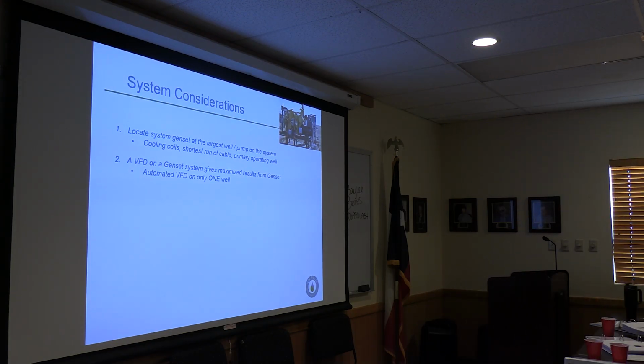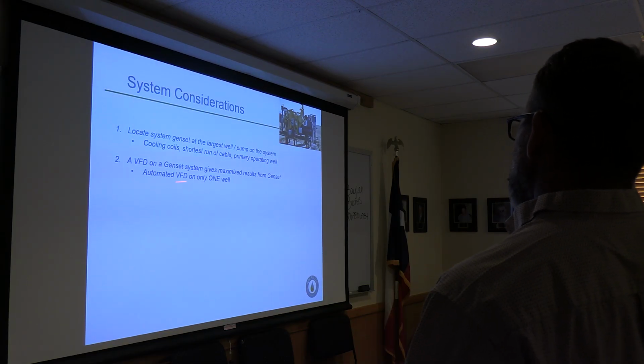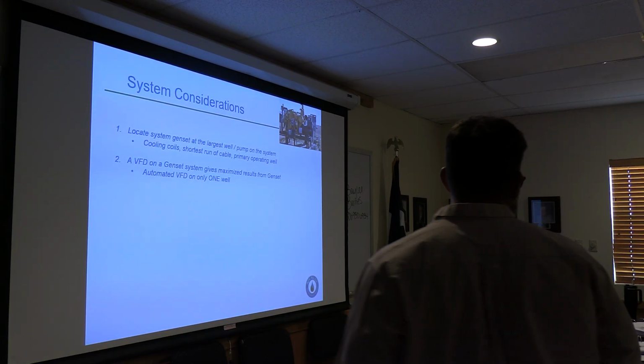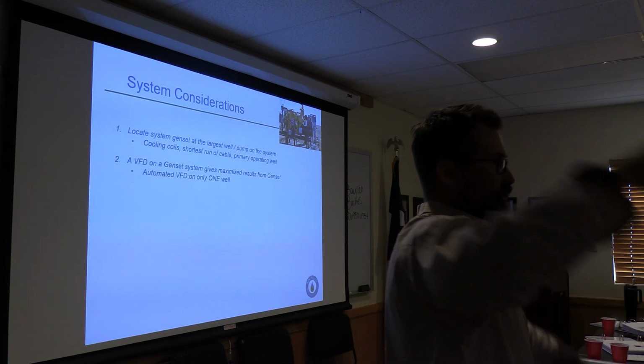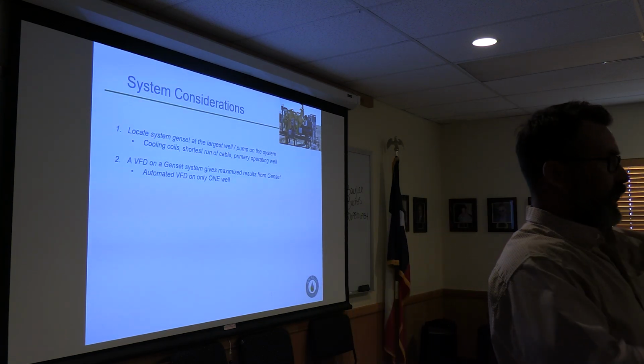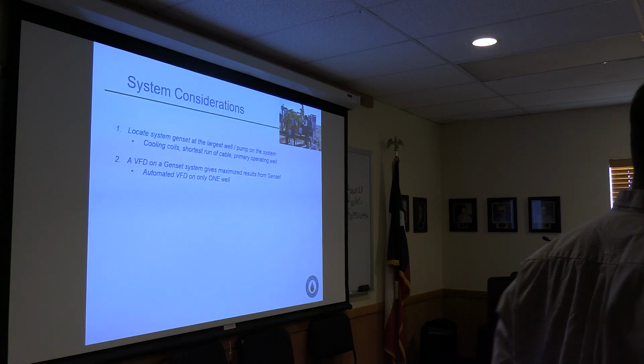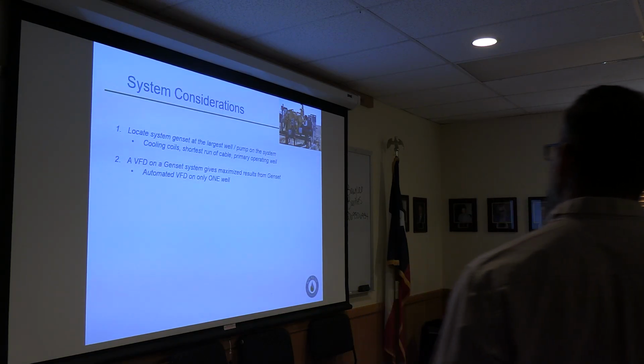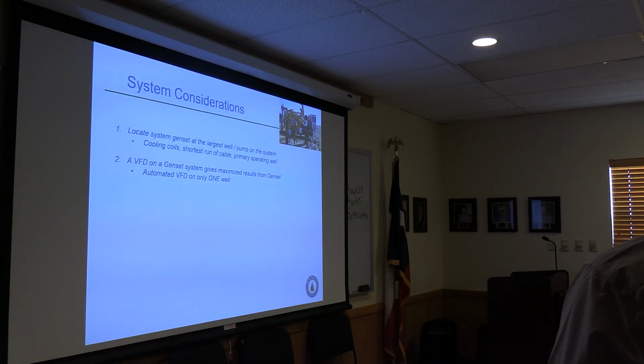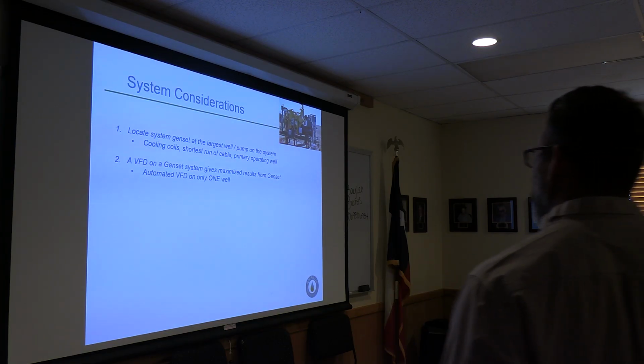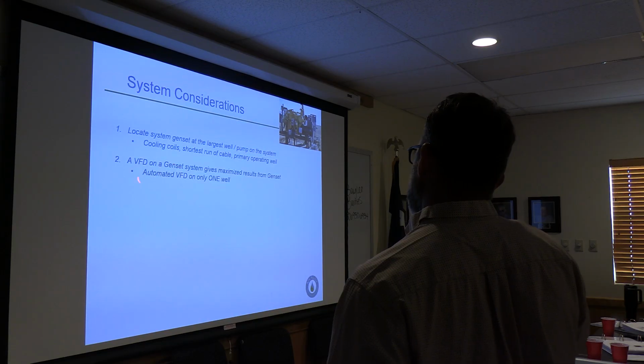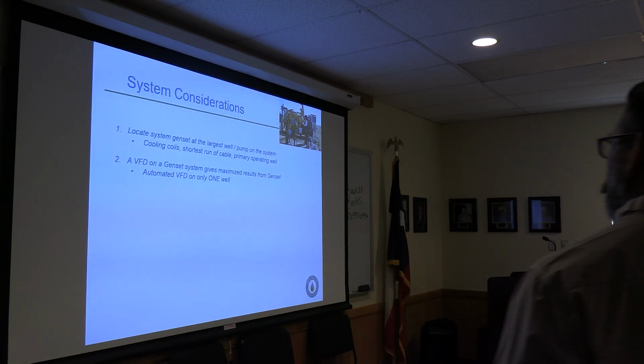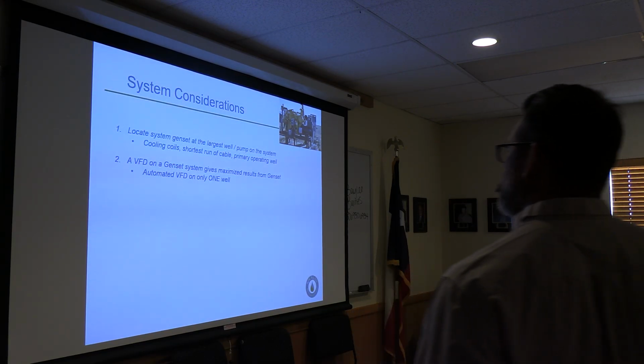If you're going to automate a VFD based on a pressure transducer to balance your system out, and this is good practice anywhere you're using drives, automate a VFD on only one well. If you don't, you create this hysteresis where these VFDs start making corrections and they fight each other. And they will go into almost an infinite loop, and they will get farther and farther off from equilibrium the longer you go. So be strategic, place an automated VFD on only one of the wells. Use drives on all of them, but an automated one on only one.